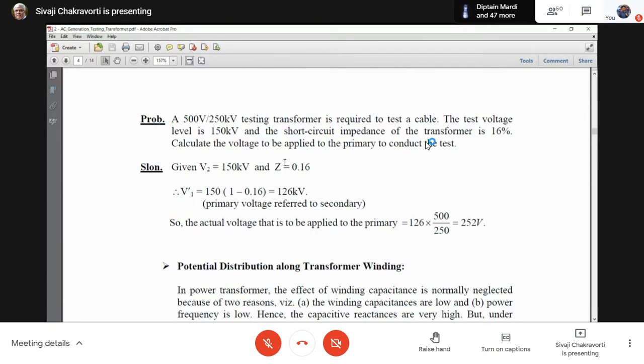The test voltage level is 150 kV. That means 150 kV has to be applied to the cable. And the short circuit impedance of the transformer is 16%, that is, Z is 0.16. Calculate the voltage to be applied to the primary, that means the low voltage side, to conduct the test. Because remember, it is always easy to measure the voltage at the primary, because the primary voltage is 500. Now, to test a cable has an interesting implication, because a cable draws mostly capacitive current. So it is indirectly saying that you should take it as a negative voltage regulation.